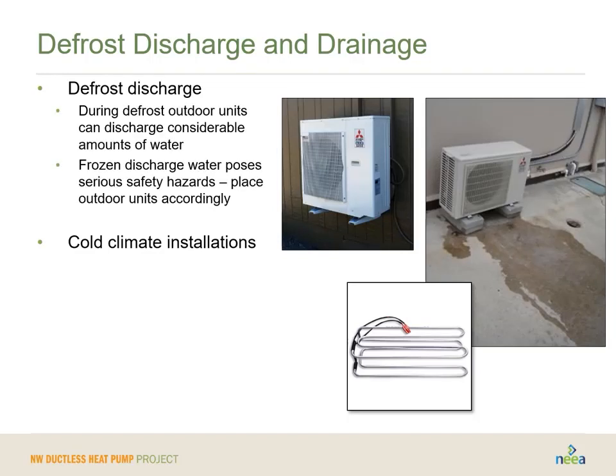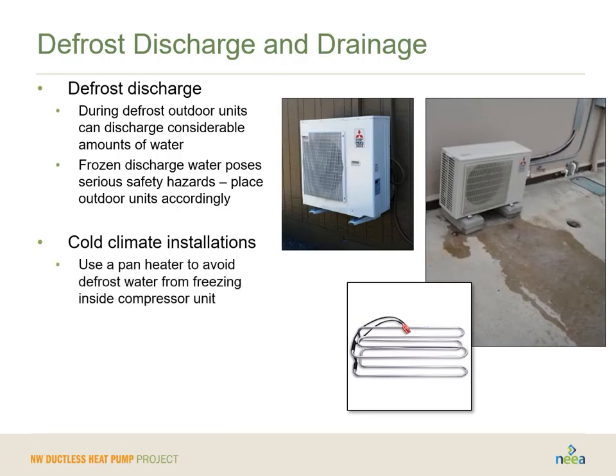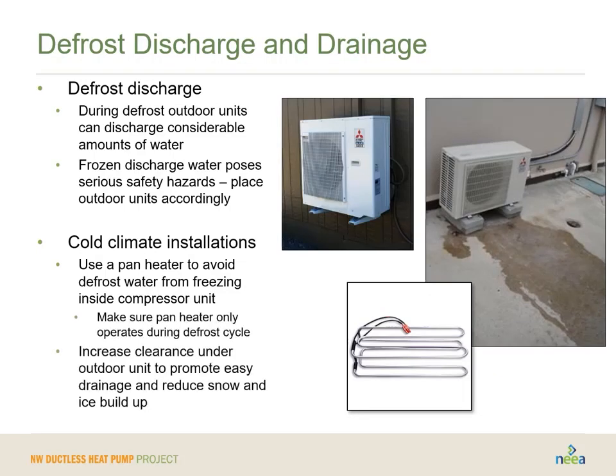Remember, during defrost, outdoor units can discharge actually a fair amount of water, and there really could be some freezing hazards with that. And make sure again that if you're installing the pan heater, it only is going to come on during defrost cycle.